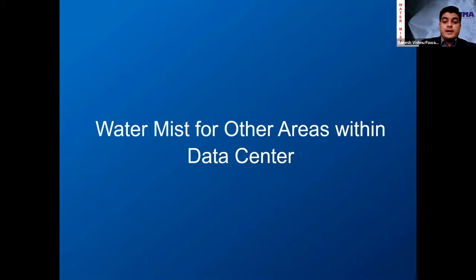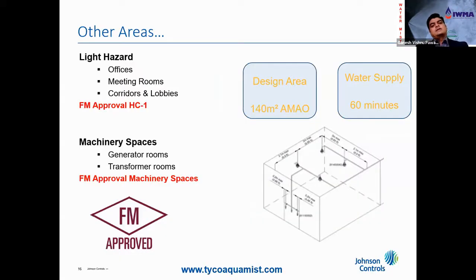So what about the other areas? Light hazard occupancies such as offices, meeting rooms, corridors, and lobbies can be protected as per HC1 approval, where we consider 140 meters square of assumed area of operation. And again, the water duration has to be 60 minutes.